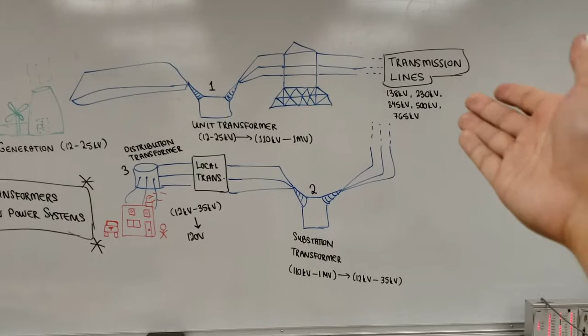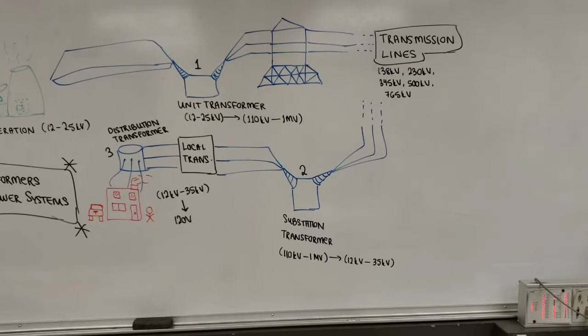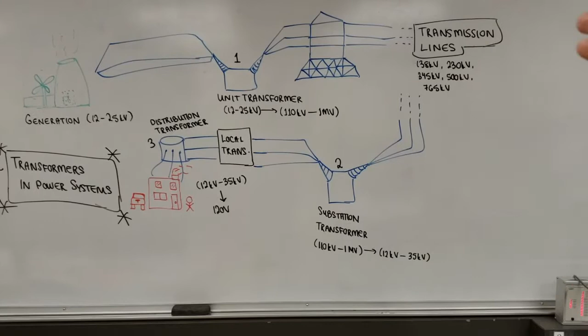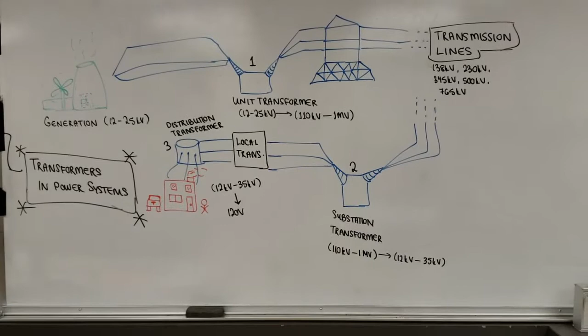It takes that 12 to 25 kilovolts and bumps it up to 110 to 1 megavolt. This bumping up heavily reduces the power losses, because now the current is down by the same factor, and losses are primarily I squared R losses - those go down by the square of that factor. So now we have a ton less losses.